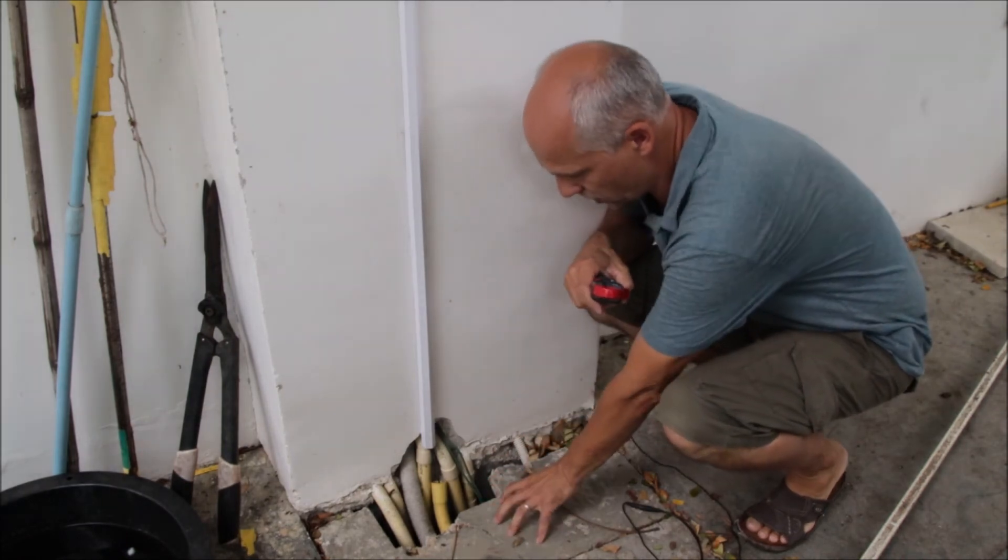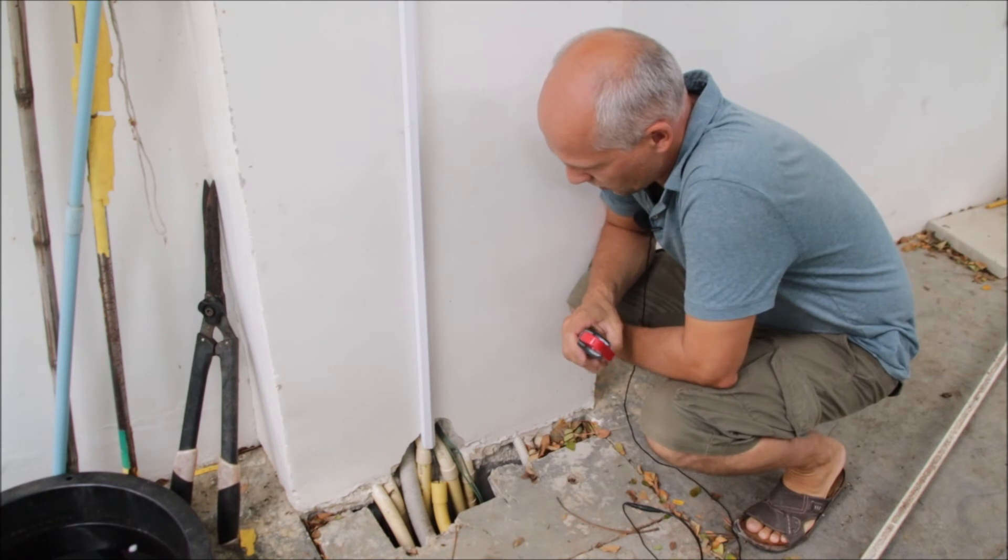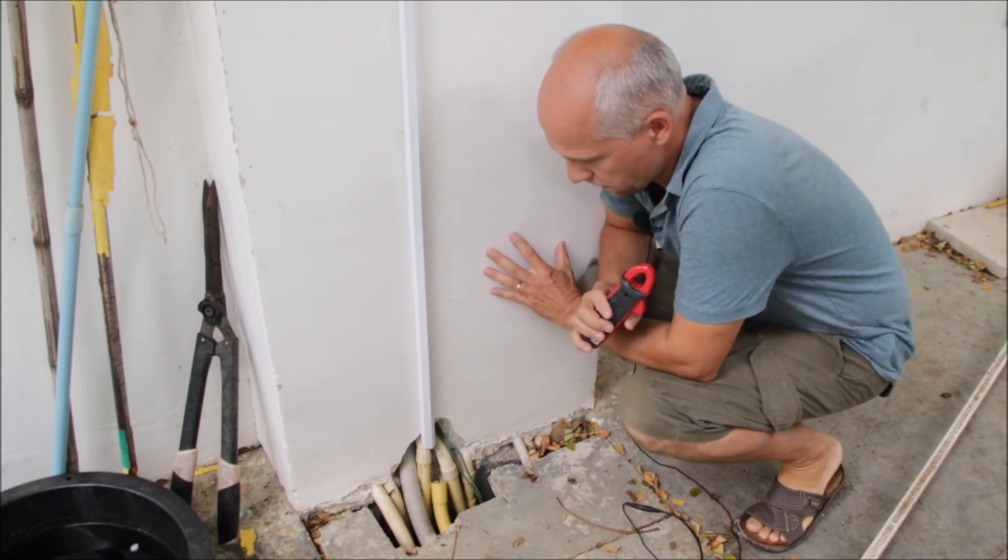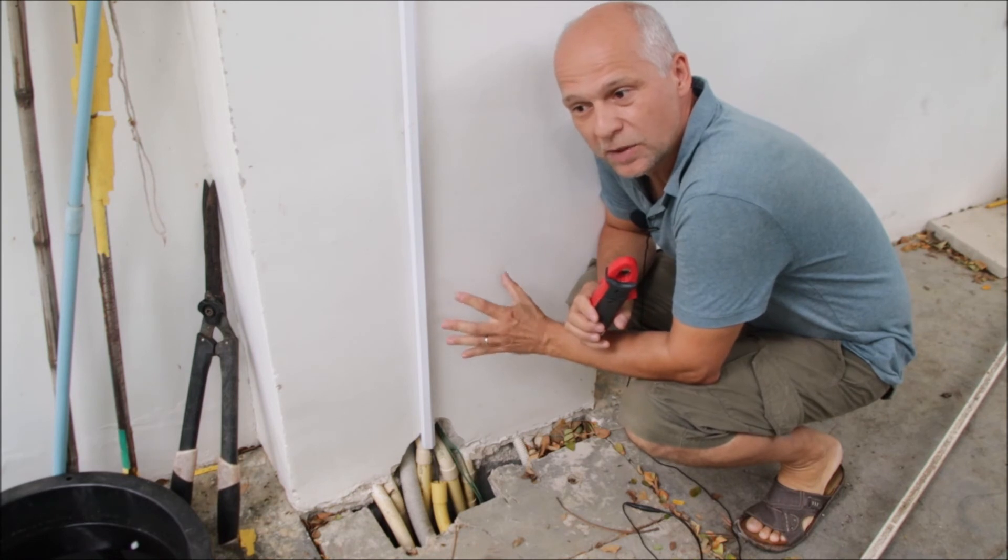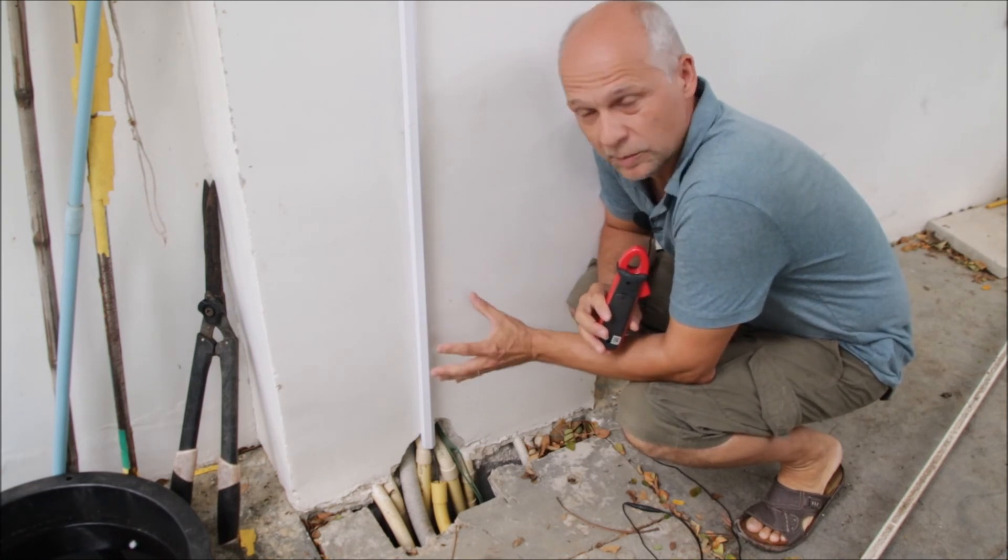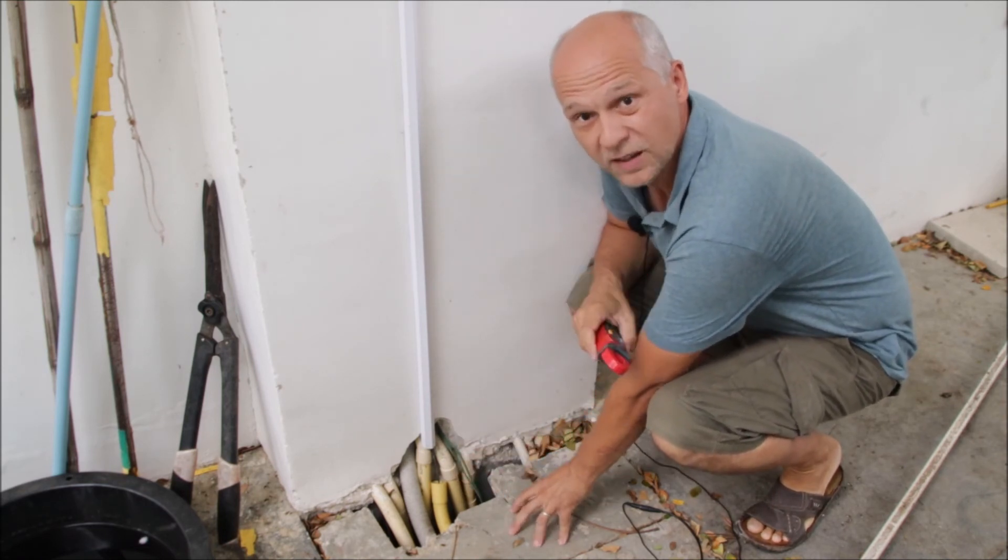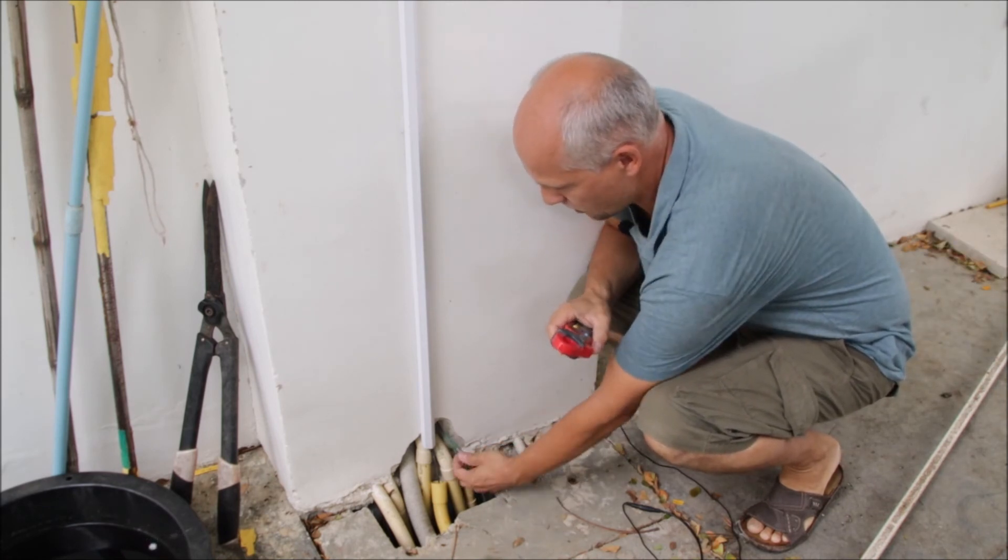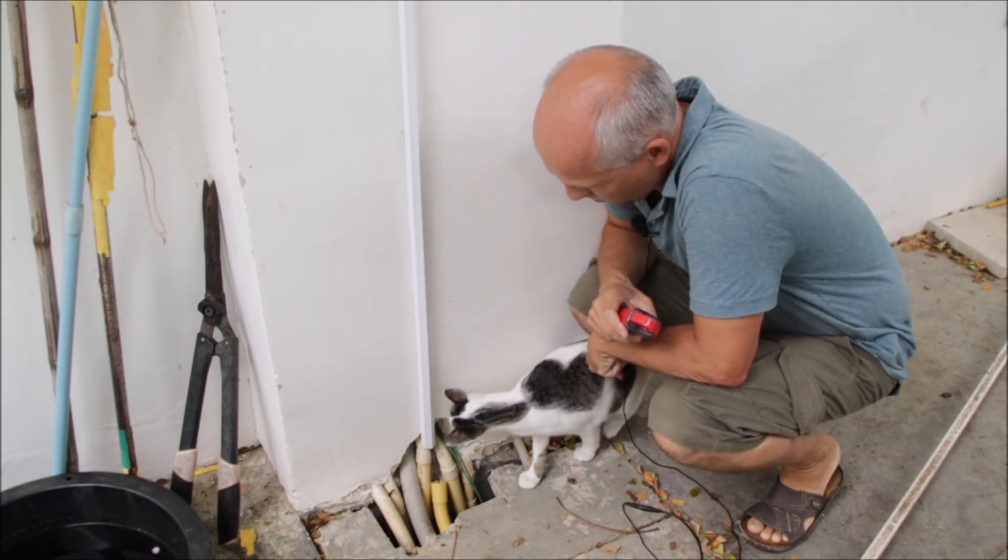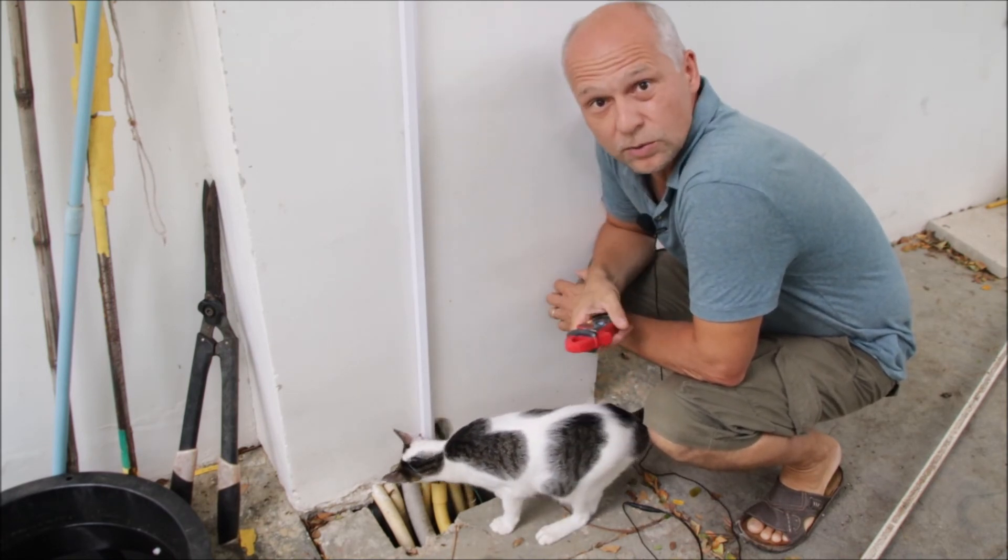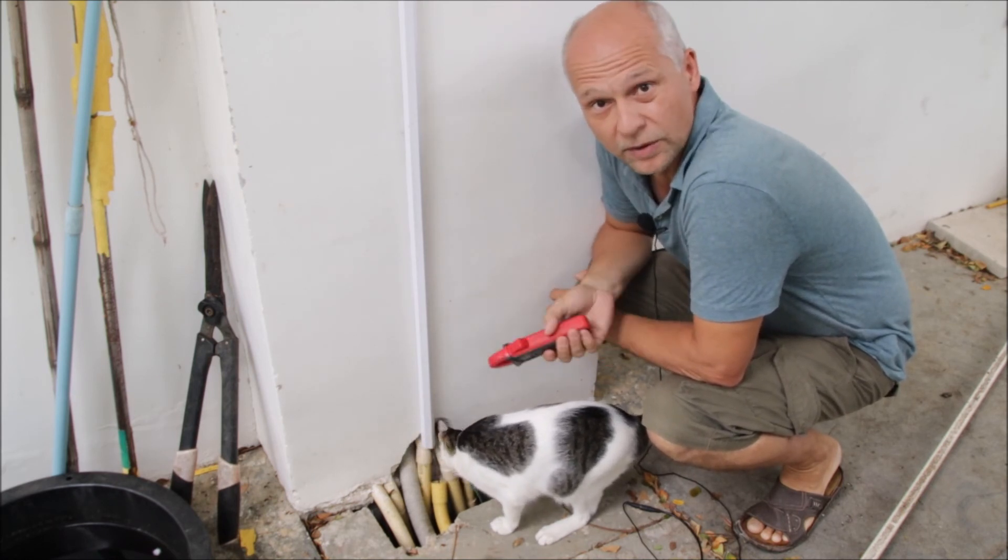Here in this trench underneath this cover, there's my grounding rod. And all the grounding of this building, which is a TN-C system, so that the main grounding is actually coming from the PEN conductor, from the transformer. But here I have an additional grounding rod within an alternative grounding point. And here I have these two wires and the cat, which is very curious, which are going to that grounding rod. And what we are going to do is, we are going to check if there is some current flowing there.